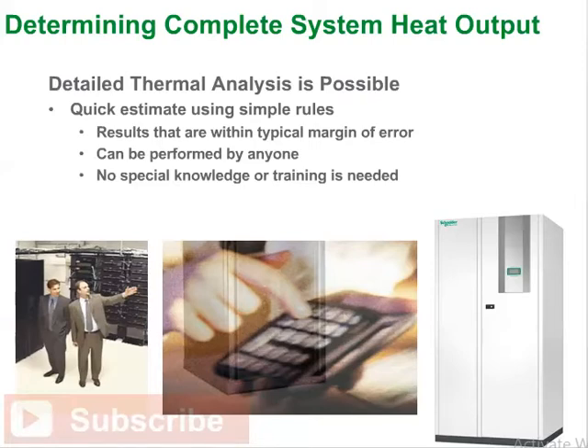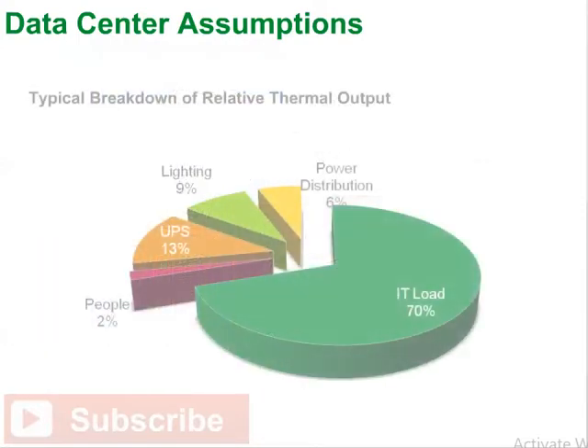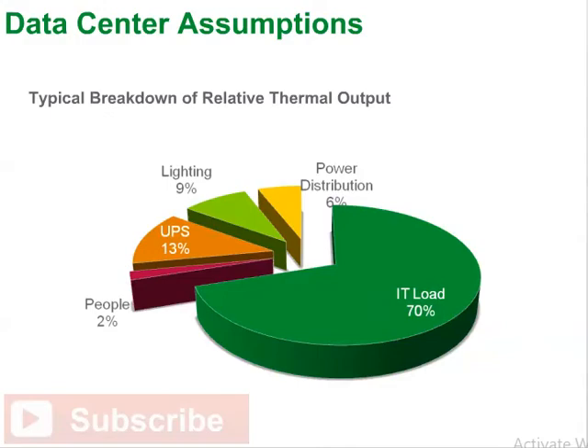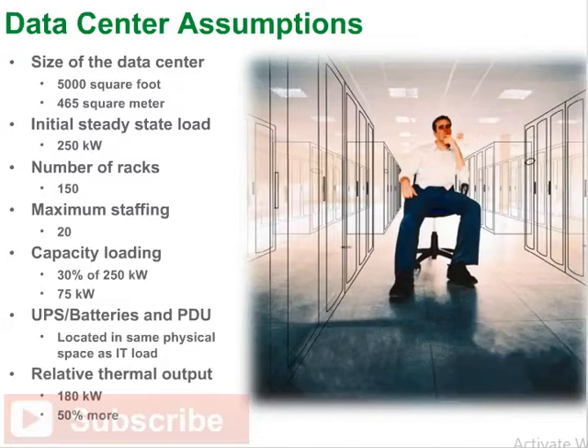Let's begin calculating total cooling requirements by demonstrating the quick estimate method. This pie chart illustrates the components that contribute to heat output in the data center. For our example, let's assume a 5,000 square foot, or 465 square meter, data center rated at 250 kilowatts. It holds 150 racks and a maximum staff of 20 persons. The data center is assumed to be loaded at 30% of capacity, which is typical, giving a total IT load of 75 kilowatts.